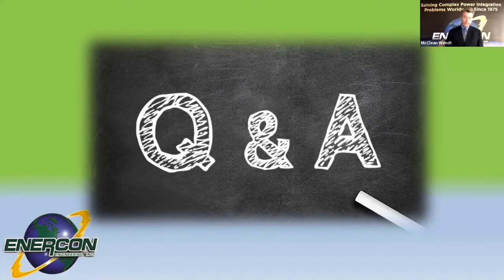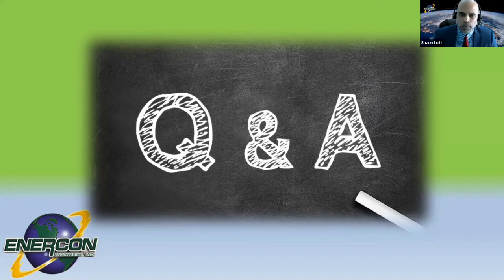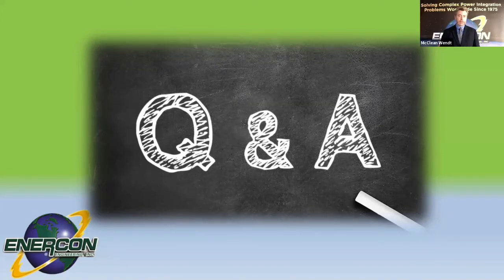Okay, so I mentioned normally we use sensing PTs. Well, I guess let's start off with just the voltage and current. So normally we have PTs, potential transformers, and current transformers on the equipment, either on the system itself that we can tap into if needed, or external PTs and CTs that we can hook into our own data capture system. So we use Fluke 1750 for data logging. It also does some power quality and harmonics recording. We also have a Dranetz meter, which also does logging and power quality. So those are the primary ones that we use. We've used Fluke NetDAQs in the past with transducers for long-term strip recording, but some of the newer meters that we have have more capability.